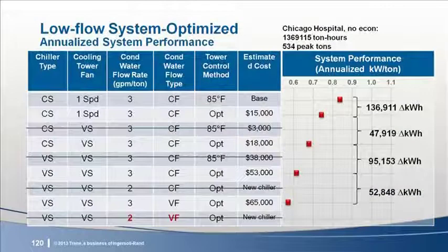Our options are to add drives to the tower fans, optimize the temperature control, add drives to the chillers, or put a drive on the condenser pump. The constant 2 GPM per ton options are likely off the table, but we can control this plant into low flow most of the time using variable condenser water flow as our option.